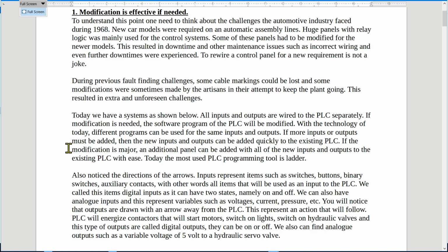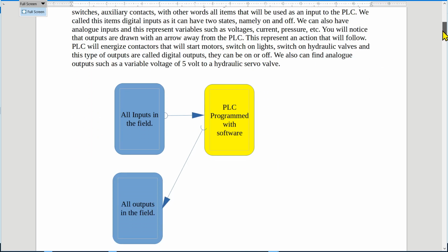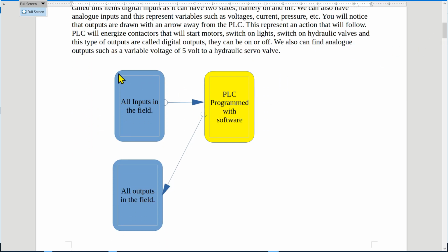Now, today, the most used PLC programming tool is ladder. Now, ladder represents no challenge to an electrician. It's equivalent to an electrical drawing. Now, let's look at this display. Now all the inputs in a field, and this is just a concept drawing, it's not the actual wiring, because in the actual wiring all the inputs in a field will be connected separately to a PLC, and the same with the outputs going down to the outputs.